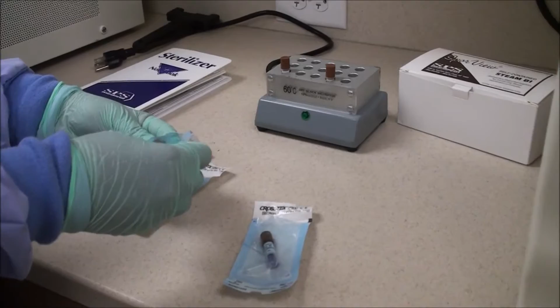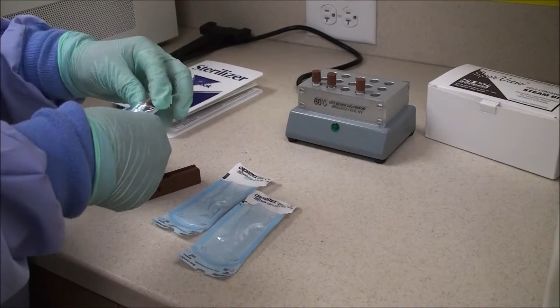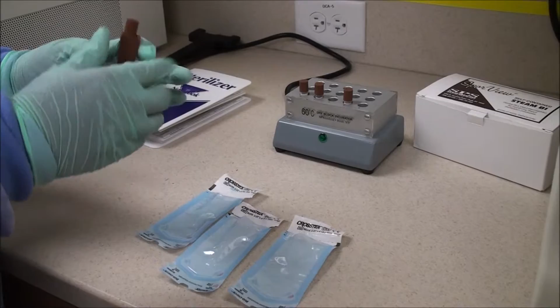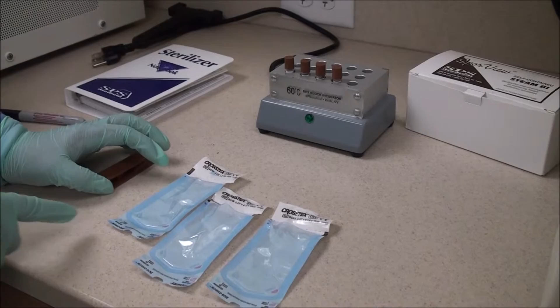In the incubator. We also need to add a capsule that has not been run through a sterilizer. This is to be labeled control, and is to be crushed before putting it into the incubator. Do this at the time you add the first capsule after it has come out of the sterilizer. The spore test should be read at 24 hours.